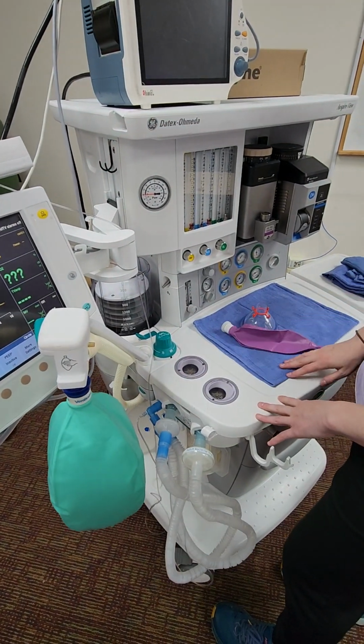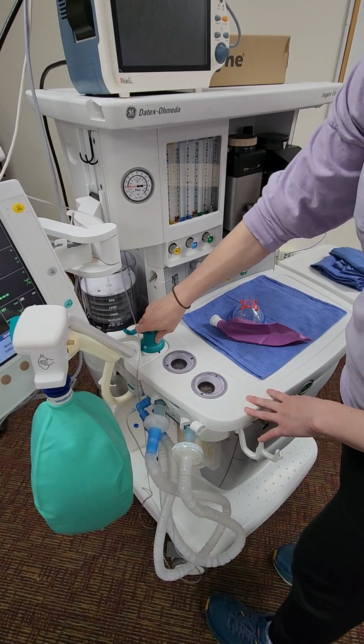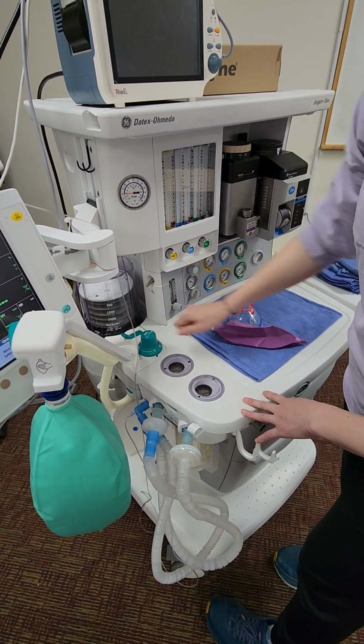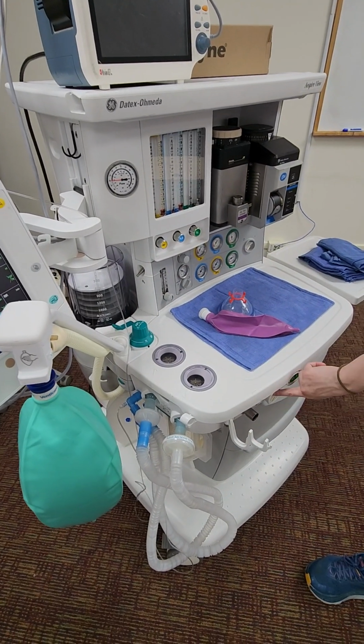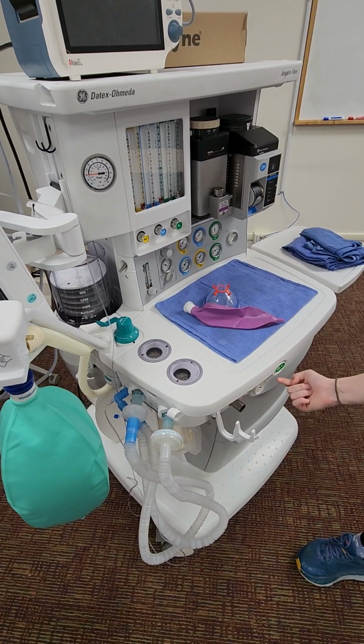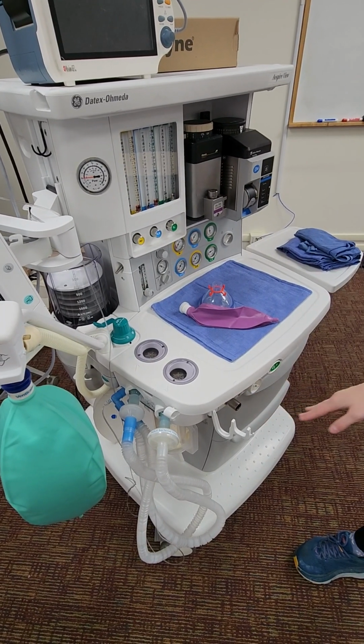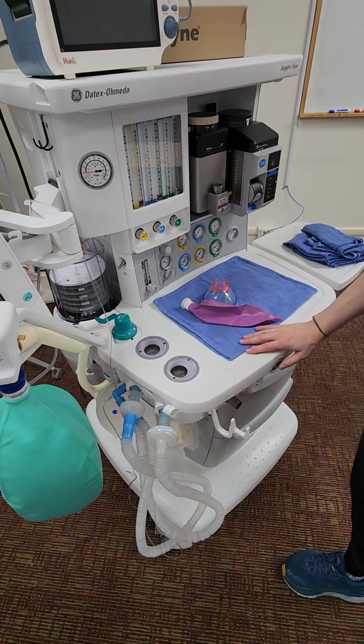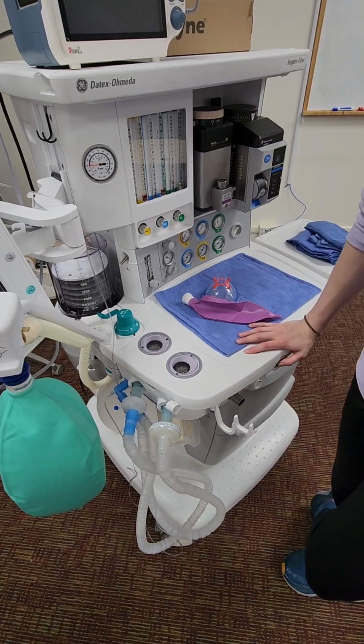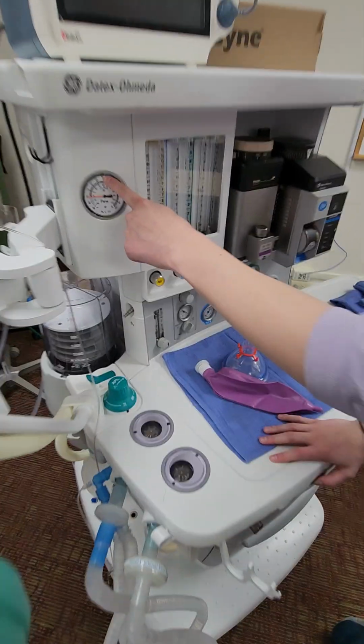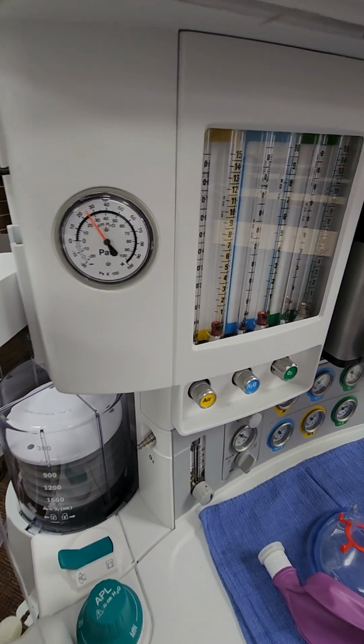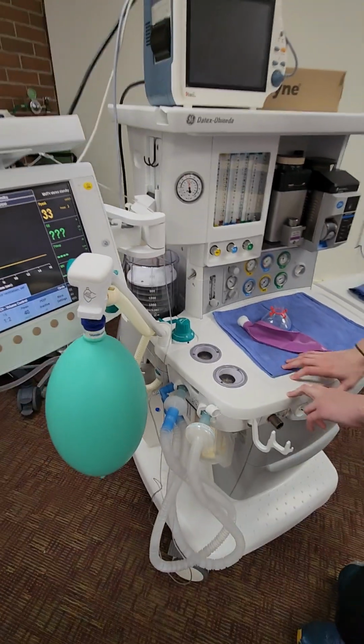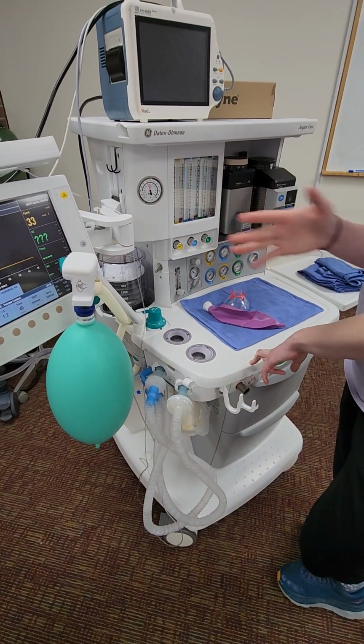So hook that up there, make sure it's occluded, and turn this all the way up. Your APL is up to 70. You double check this thing because this is often forgotten. So we have to hook this back up to our machine from our low pressure leak test. And now you can O2 flush until this reads 30 centimeters of water. So we're O2 flushing all the way up to there, and that should hold at 30 for 10 seconds.